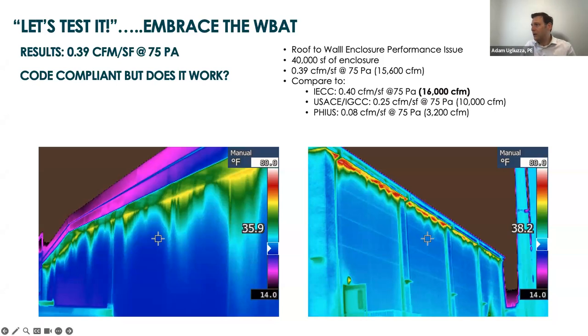So just a quick background. The IECC building code right now is 0.4 CFM per square foot at 75 Pascals. Another common industry standard, and also the IGCC: the Army Corps and IGCC require 0.25 CFM per square foot, so a little bit harder there, at 75 pascals. And then PHIUS is kind of the gold standard out there in terms of the highest level of air tightness, at 0.08 CFM per square foot at 75 pascals.